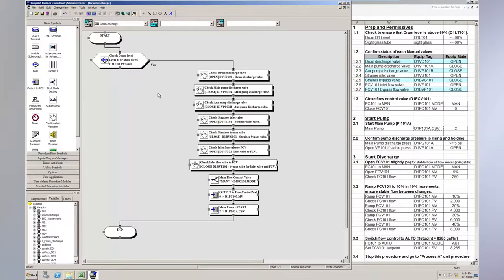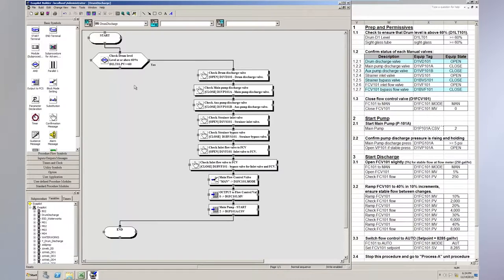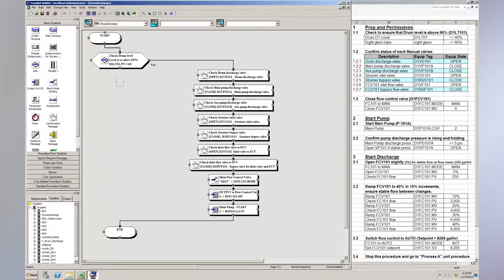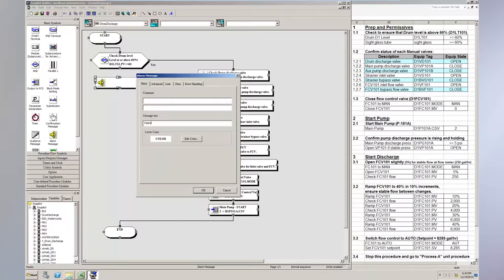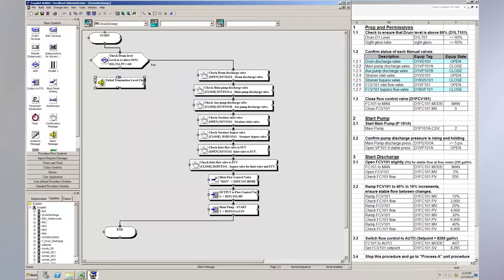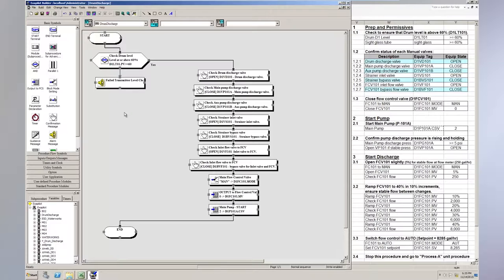So now I've completed the line if it passes the level check. But what happens if it fails the level check? For that, we want to create an alarm message. So for the alarm message, I'm just going to put failed transmitter level check. And to make it a little bit more fun for us on simulation, I'm going to give the ability to recover from this. So if you have a failed check here, I'm then going to have a confirmation message to allow the operator to try to recover from this failed check.